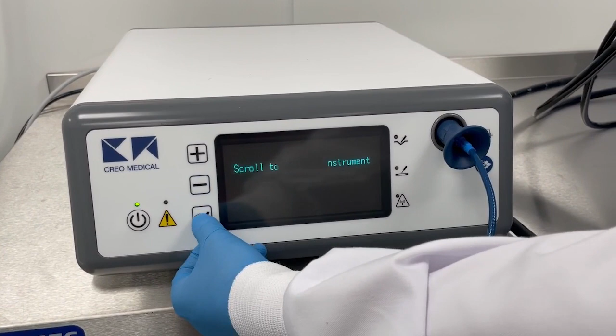You can loosen the locking knob for the catheter length adjustment. Catheter length is adjusted using the distance slider. Tighten the locking knob to lock the catheter length. Loosen the locking knob for needle actuation. Needle actuation is done using the proximal slider. You can tighten the locking knob to the desired length.